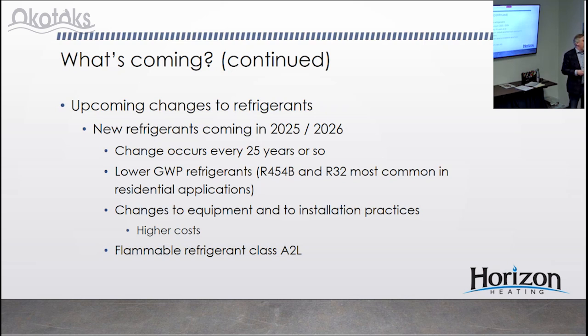And the kicker is it's going to bring your fan on to dissipate the refrigerant that's leaking, but it's also going to stop your furnace from coming on, because they don't want the flames to come on while that leak detector is being set off. So the downside is you could have a leak in your refrigerant system in the dead of winter and your furnace won't come on. So it's adding a little layer of complexity.